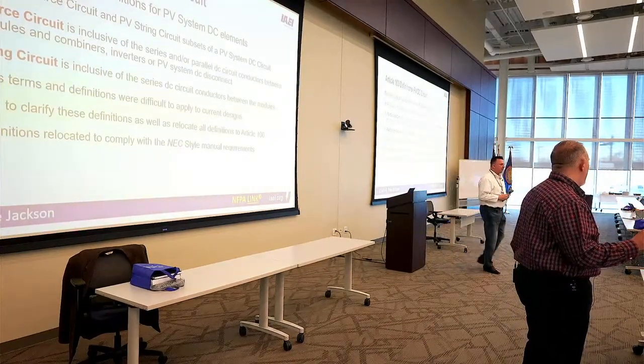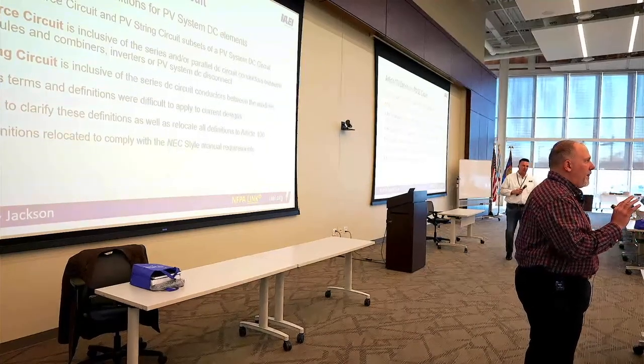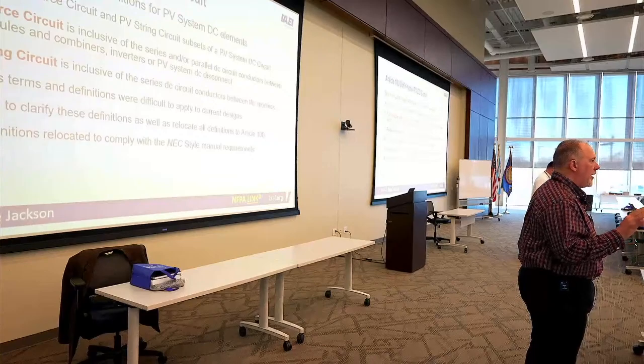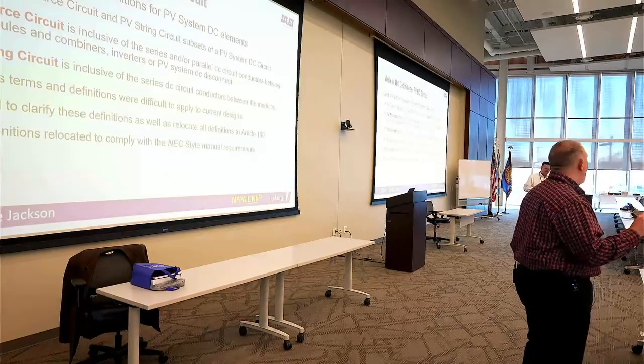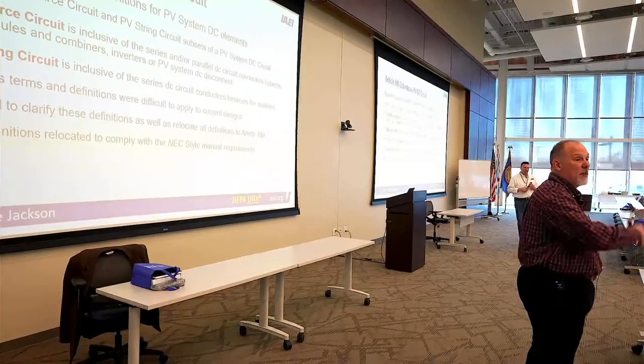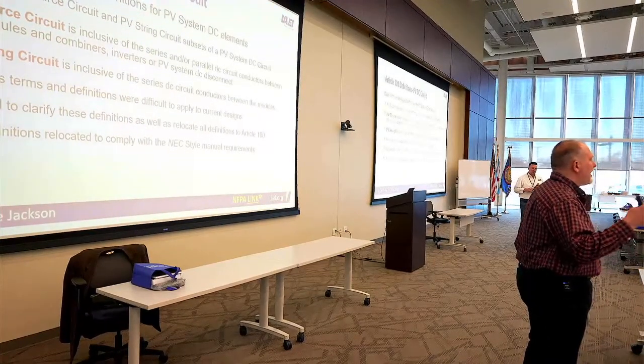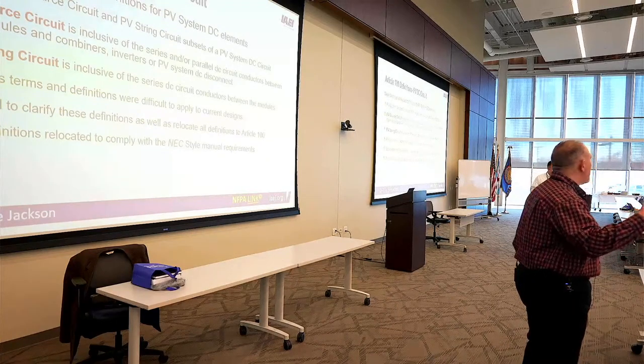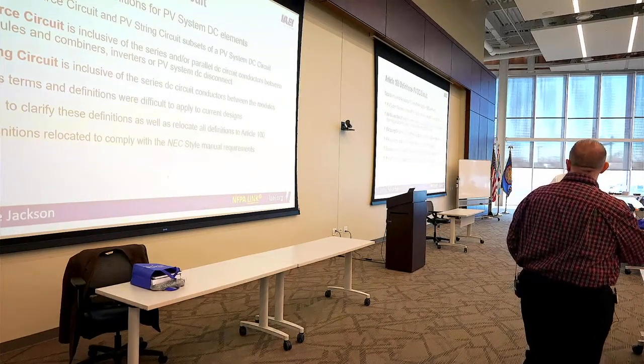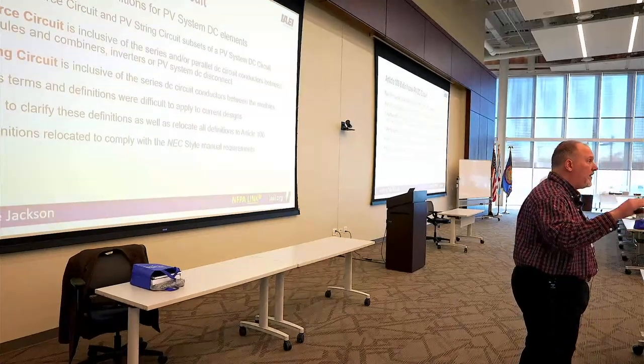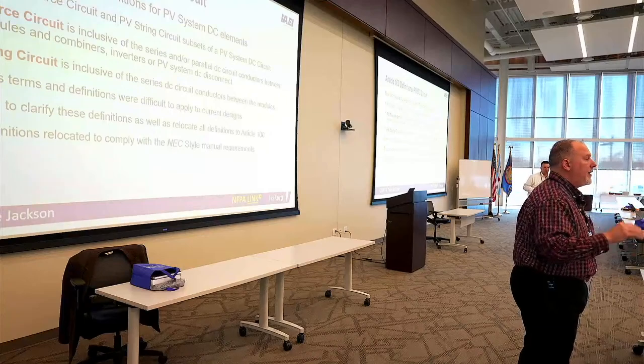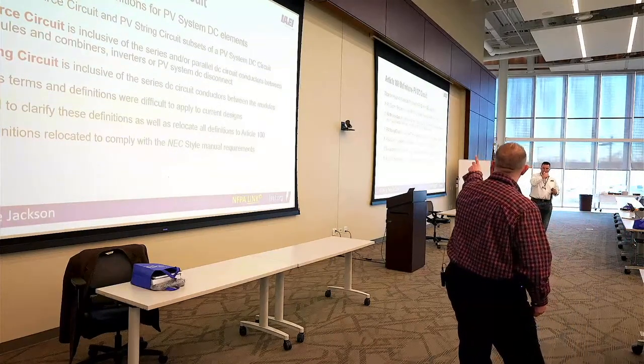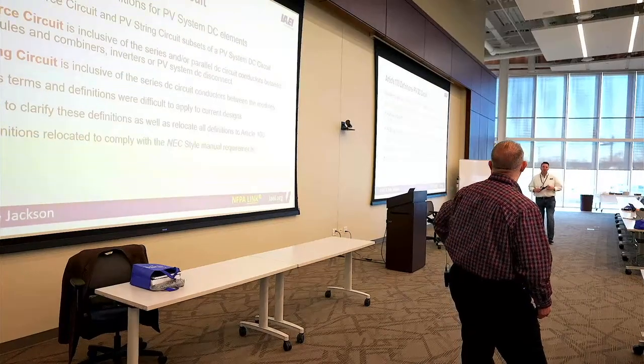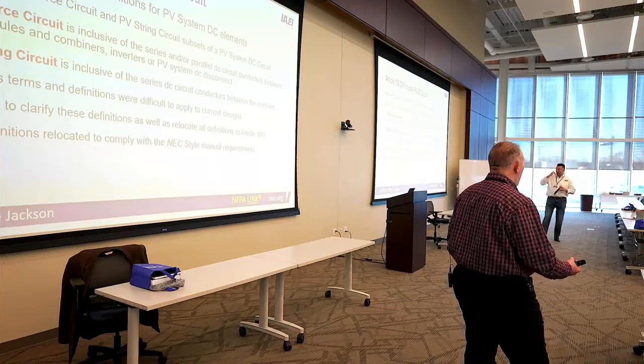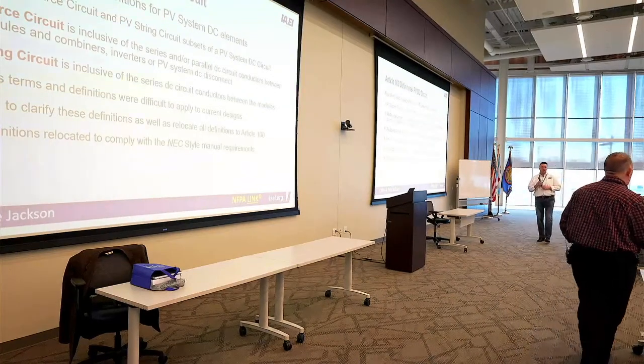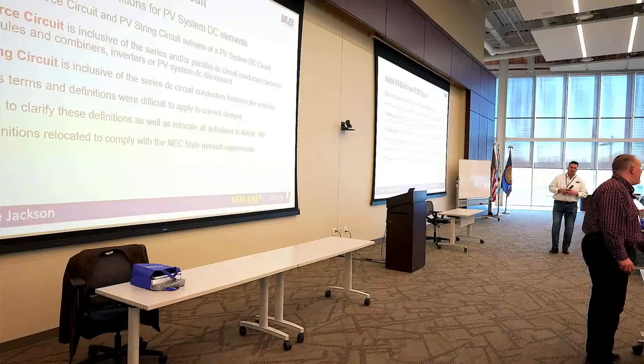So in a PV system, when you get into photovoltaic systems, they don't like to call things feeders, branch circuits, or conductors service conductors. Why? Because that brings a lot of other requirements along with it. So they're trying to keep you in the requirements in 690, and they defined a term, PV-DC circuits, with requirements around them for us to follow. They defined them as your PV source circuit and your PV string circuit. So all of your DC circuits in a PV system are now called PV-DC circuits, and they changed the requirements in 690 to help you understand what you need to do to properly protect a PV-DC circuit.